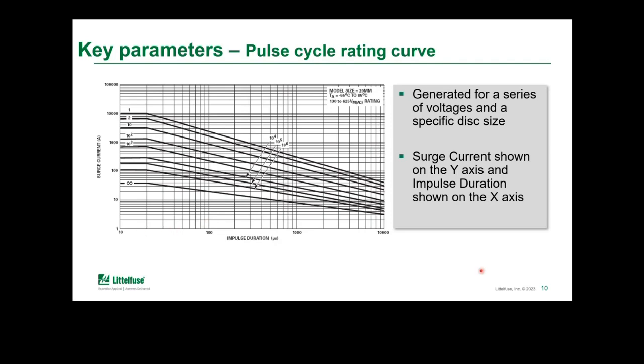Now, if we decrease the peak current, say to 1,000 amps, then we can handle up to 500 pulses. So we have a much greater pulse life for lower peak current values. But this also changes as we increase pulse duration. As the pulse duration increases, the capability begins to decrease. So these are all factors that need to be taken into consideration when we start looking at selecting MOV products.